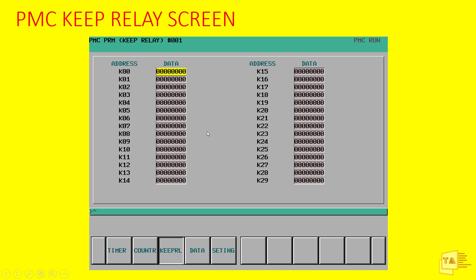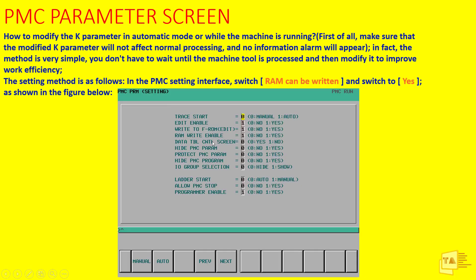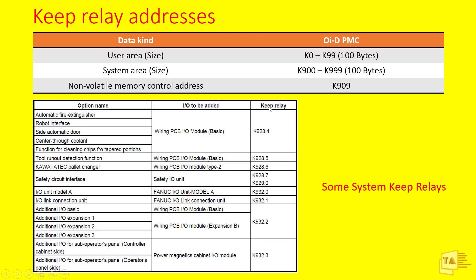If the machine is running in auto mode and you're getting an alarm that needs to be shielded, it is possible to modify the K Parameter while in auto mode. However, to do this you must enable RAM Write Enable — set it to 1. If RAM Write Enable is 0, you cannot change the K Parameter in auto mode. Once you set RAM Write Enable to 1 and confirm yes, you will be able to modify the K Parameters while the machine is running.